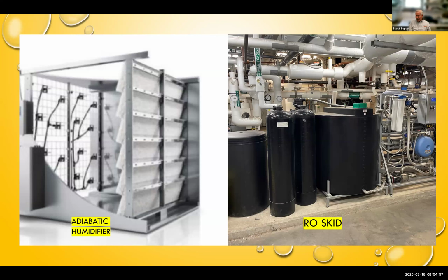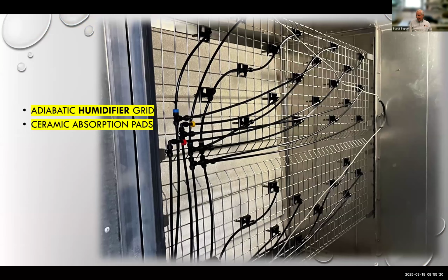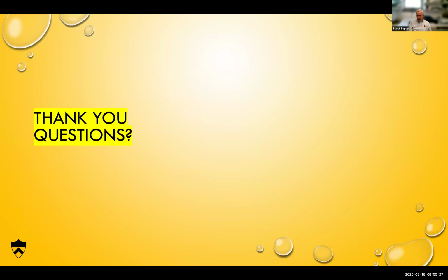The drain pans and walls of the air unit should be stainless steel because it's aggressive water. Absorption efficiencies are not as good as with isothermal humidification, and there's also reject water during the production of the RO water, but you might be able to recover that water into a gray water system. And the maintenance of this skid requires attention. And this is another picture of the grid and the nozzles. And that's it. I might have run out of time.